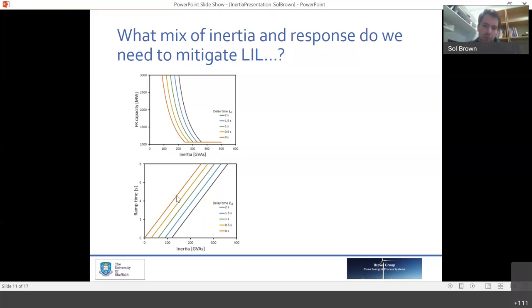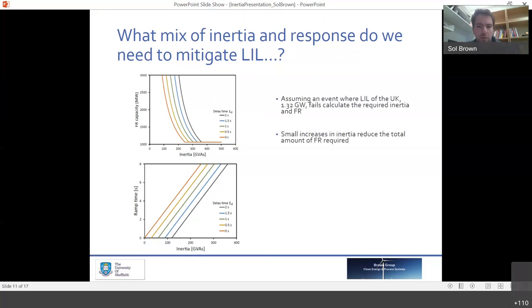And the ramp times of the responsive generation, representing maybe a battery or something like a gas turbine, similarly, if they're slower, then with the increase in the delay you require a faster ramp time to get you up to speed. And if your ramp time is not there, you need a greater amount of inertia to protect your system. So assuming that we're at the 1.32 gigawatts for a largest infeed loss, then small increases in inertia reduce the total amount of frequency response required. That's just the shape of the curve on the top left.